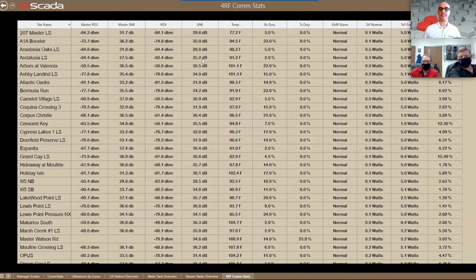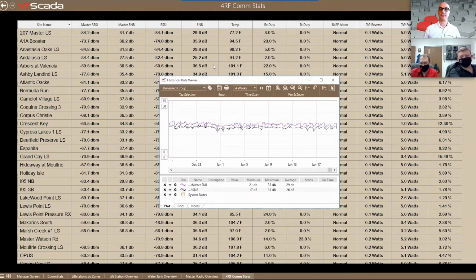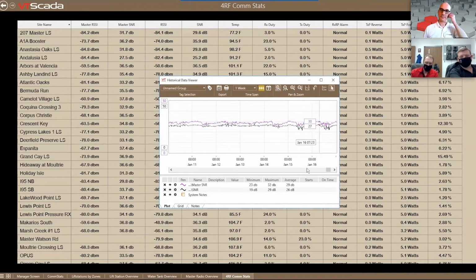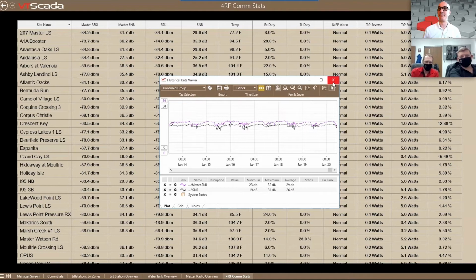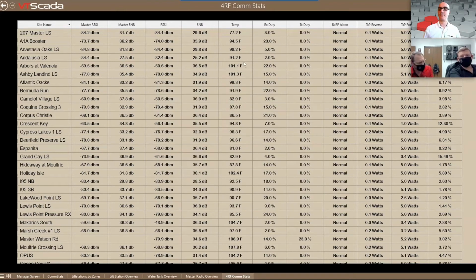The trends - the radios we use, the 4RF radios, have a rudimentary way of trending, but it's nowhere near as detailed as this. These screens update every 15 minutes. We have the polling rate set to every 15 minutes so it's not overboarding the rest of our system, but the radios only let us look at the previous 24 hours. There's another rudimentary trend that lets us go a little further back, but it's nowhere near as detailed as we're able to do with the VTScada screens.